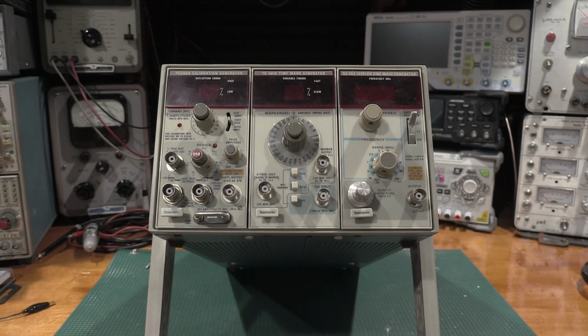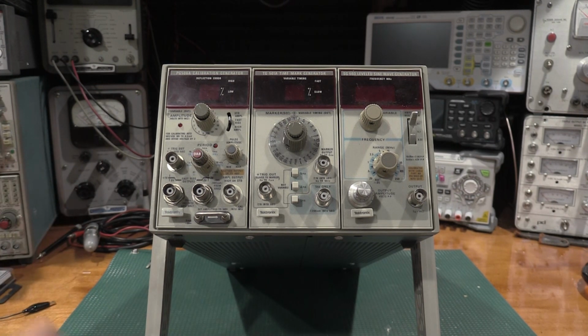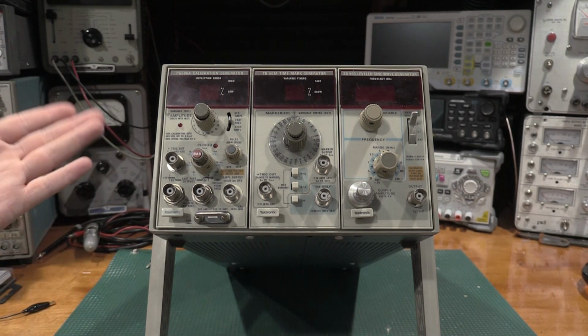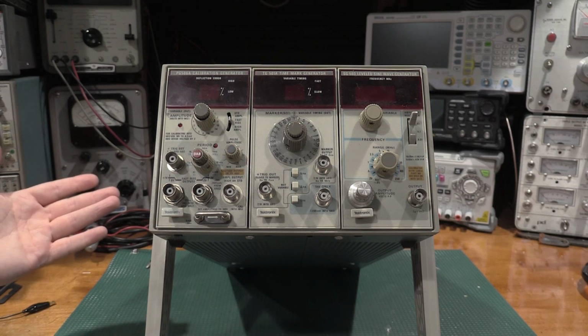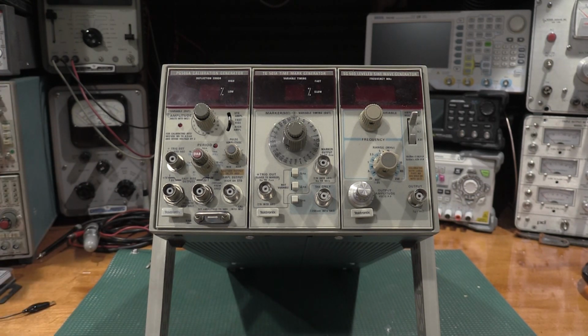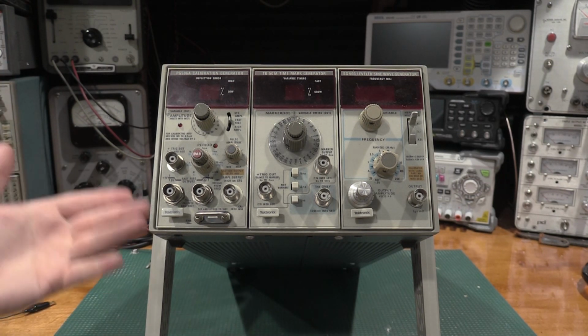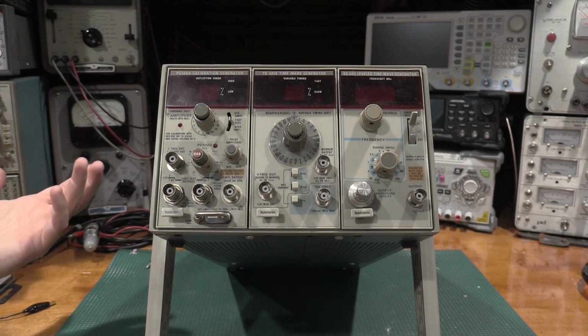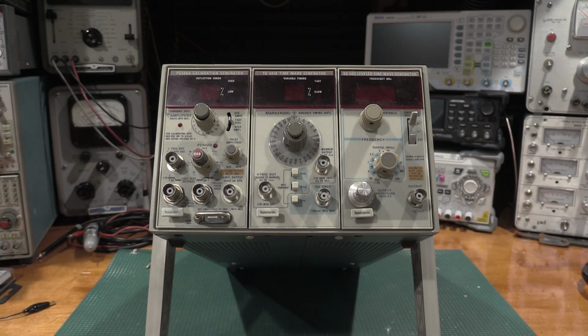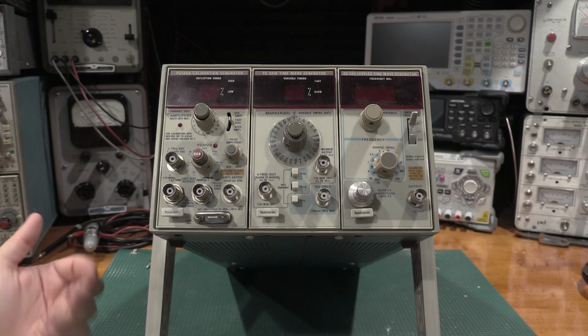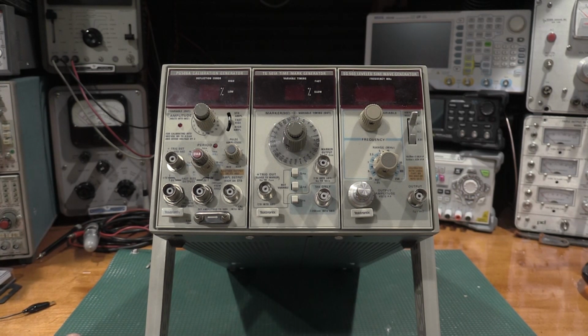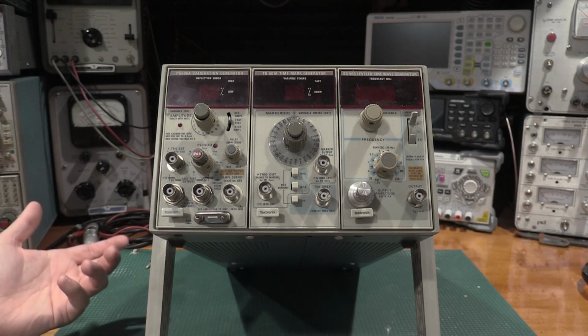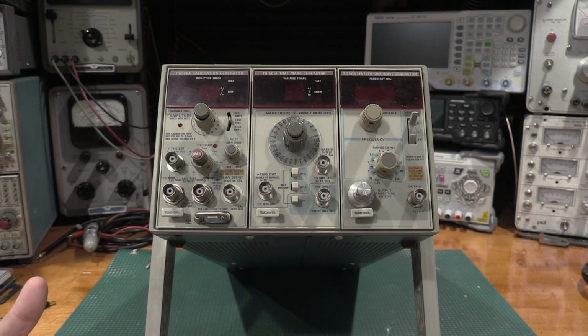The problem is you run into a chicken and the egg kind of issue. When you buy one of these, you want to validate the plugin, but you need better gear to validate the plugins than the plugin. But these are the standards of which you calibrate a scope with. So they're usually the best someone has in the lab. So how do you find better gear to calibrate these, to calibrate the calibrator?